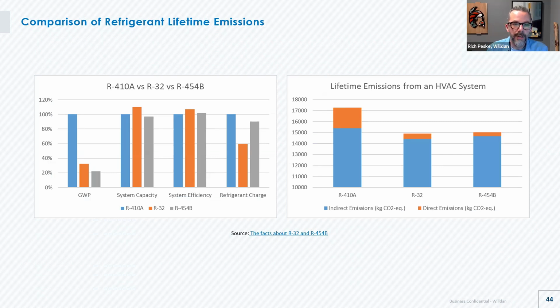Okay, so we did some comparison of overall emissions with the different refrigerants, and it's a little bit of an eye chart in terms of the global warming potential here on the left, where you're seeing blue as R410A, orange as R32, and gray as R454B, a lot of numbers and letters here. Global warming potential goes down as we move to the right. The system capacity and efficiency can be kind of similar. The refrigerant charge may be a bit less with R32 than some of the other ones. And jumping back up with R454B.